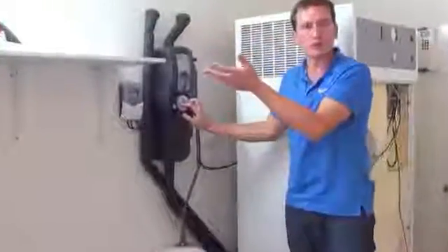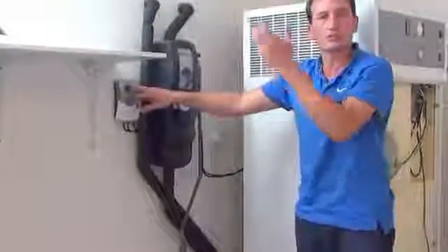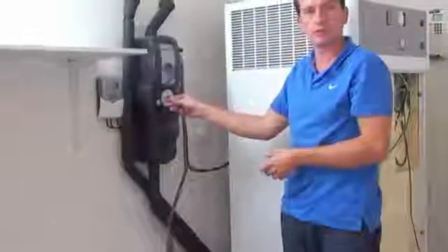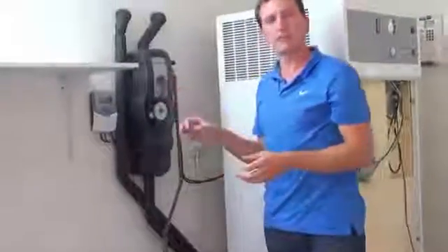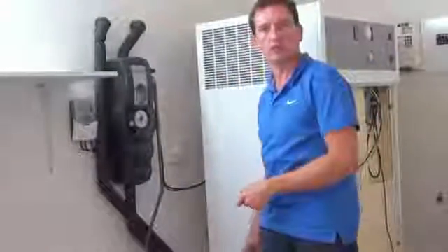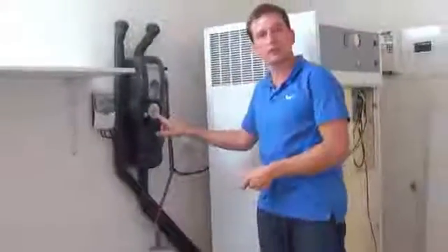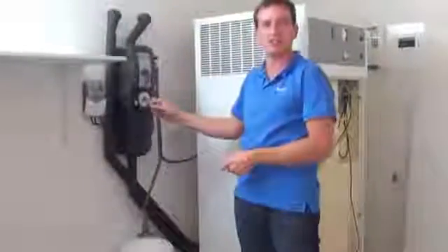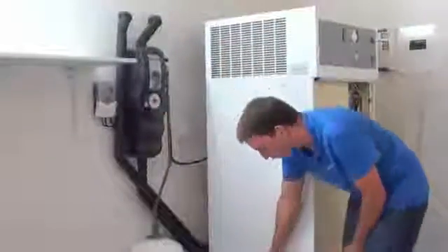The minute the temperature gets lower, this computer will sense that the temperature on the panel is lower and it will automatically switch this off. This is a very efficient system because if there's even 1 degree difference, if the panel is 1 degree warmer than the water in the bottom, it's automatically going to start the circulation pump, and we're going to harness the energy out of the sun and transfer it into the bottom.